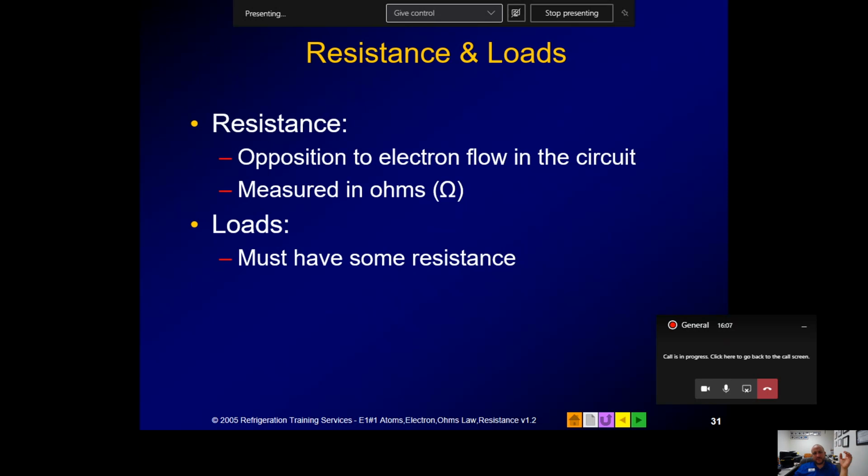All right, so what is resistance in the first place? Resistance is measured in ohms. We learn how to do that with our meter to check ohms across something. When we set it to ohms or resistance, not only are we measuring resistance, but we're also measuring continuity. It's showing that those two points are continuous, that they're touching each other, or that they're open, right? So you've got different readings on your meter. You could have an OL. OL means open loop, which means that they are not connected. Zero ohms means that they are connected, but there's no resistance.